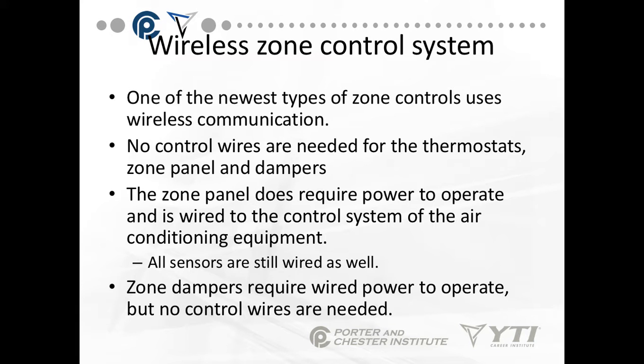One of the newest types of zone controls uses wireless communications. No control wires are needed for the thermostats, zone panels, and dampers. The zone panel does require power to operate and is wired to the control system of the air conditioning equipment. All the sensors are still wired, and the zone system dampers require wire power to operate, but no control wires are needed.